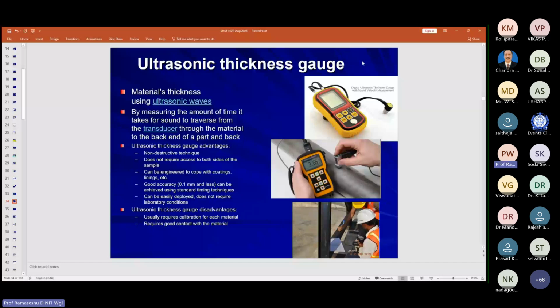Such thickness measurements are required whenever tanks are used for storage of hazardous materials. Over time there is damage to the material and thickness may get reduced. If you do not assess this reduction, there will be sudden failure of the storage tanks. That's why periodically they inspect the thickness of cylindrical storage tanks at different locations to find the average thickness. For such applications, this instrument is very low cost but very useful.